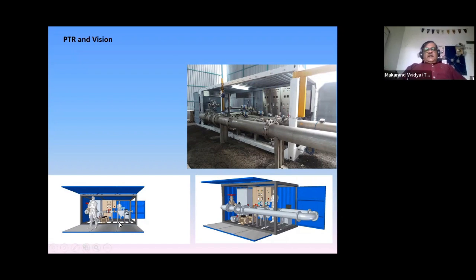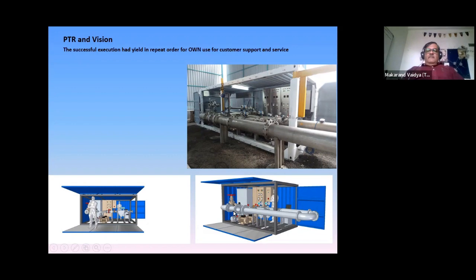And this is a typical skid actually. And this is a typical assembly, I think 8-inch. And here you can see a multi-class flange: 150 class, 300 class, and 600 class. All three PCDs are drilled over here, so a 600 class unit also can be fitted over here. And this is a flexible pipe fitting in which you can increase the distance between these two flanges and fix the unit under test over here, depending on the size.